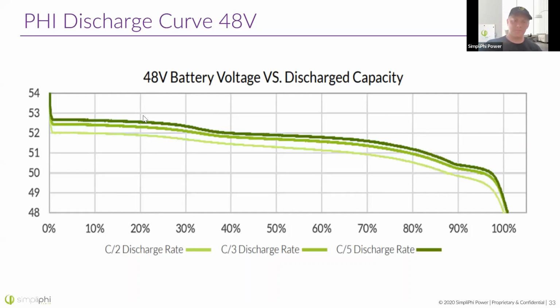Again, just explaining here, it's so hard to tell the state of charge from just reading the voltage because let's say you look at a battery voltage and you see 52.7 volts. Now that could mean that you have a C/3 discharge rate and a battery at 50% state of charge. It could also mean that you have a C/2 discharge rate and a battery at 70% state of charge. It could also mean that you have a C/5 discharge rate and a battery at 30% state of charge. So this is why the load or charging speed really impacts the way that voltage is going to sit.